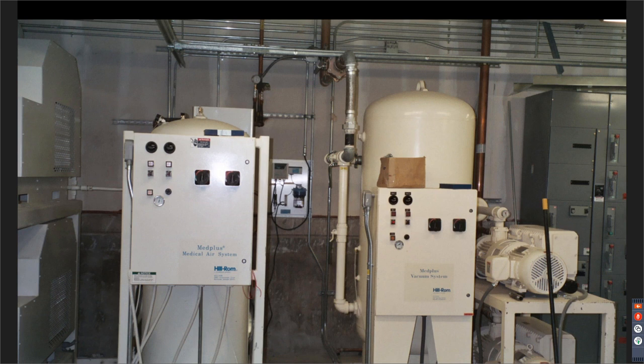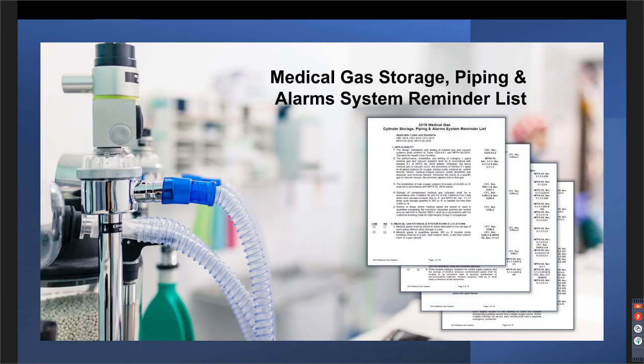These gas systems, of course, include vacuum as well as medical air. So the specific requirements for these specialties are also found in NFPA 99. I share all of these items because OSHPD does have a very comprehensive medical gas storage, piping, and alarm system reminder list. And we update this list every code cycle. So the ones that have been published recently have all of the updated code requirements. And in my experience, when you use these checklists and even include them with your plans that get submitted to OSHPD, it shows that you're doing your due diligence and that you've looked at and taken into account everything that is required, which in general speeds up your review process pretty significantly.